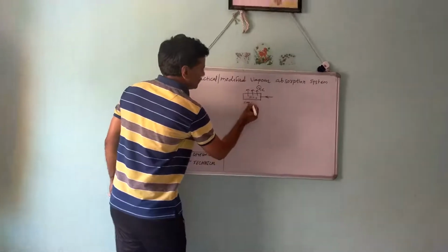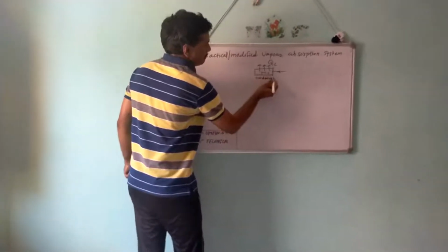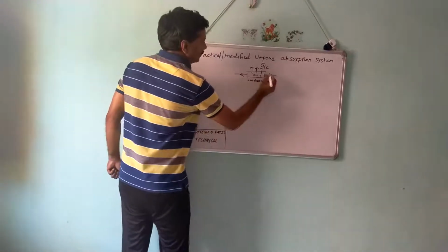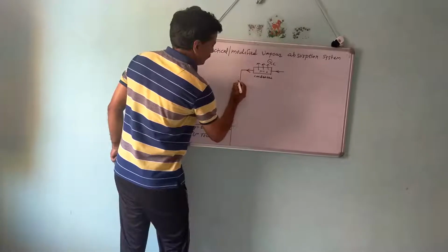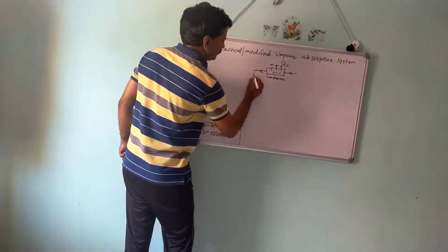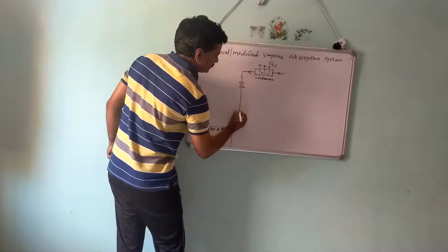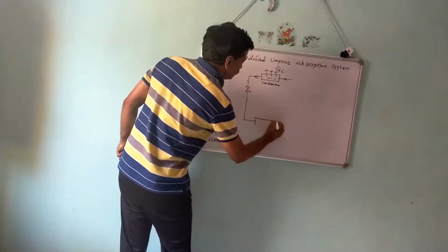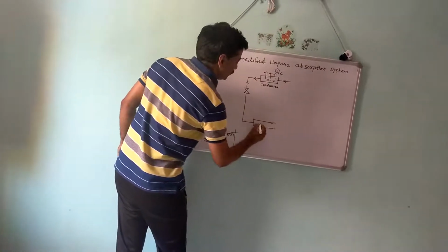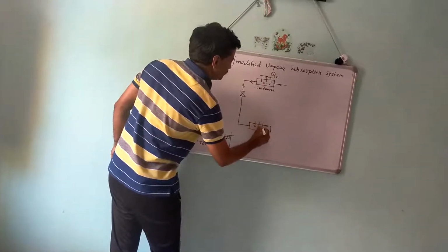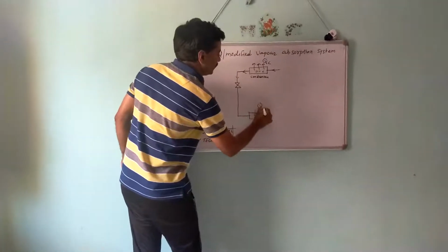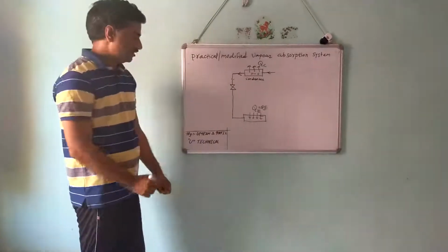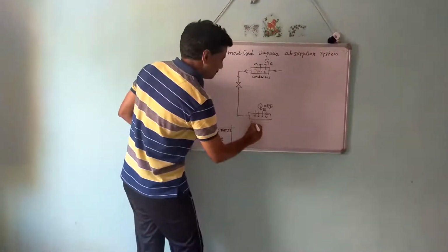So this is a condenser, and then this condensed ammonia is passed through an expansion valve. It is expanded here, and this expanded refrigerant, that is low pressure low temperature refrigerant, will enter the evaporator. It will start to absorb heat, and thereby it produces the refrigeration effect, and this amount of heat absorbed is nothing but the refrigeration effect. So this is the evaporator.